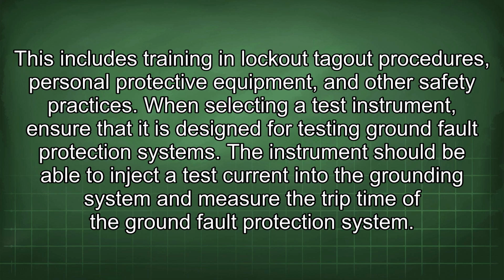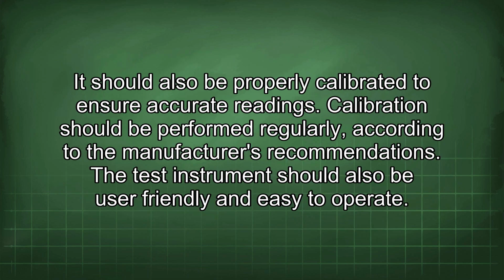When selecting a test instrument, ensure that it is designed for testing ground fault protection systems. The instrument should be able to inject a test current into the grounding system and measure the trip time of the ground fault protection system. It should also be properly calibrated to ensure accurate readings. Calibration should be performed regularly according to the manufacturer's recommendations. The test instrument should also be user-friendly and easy to operate.